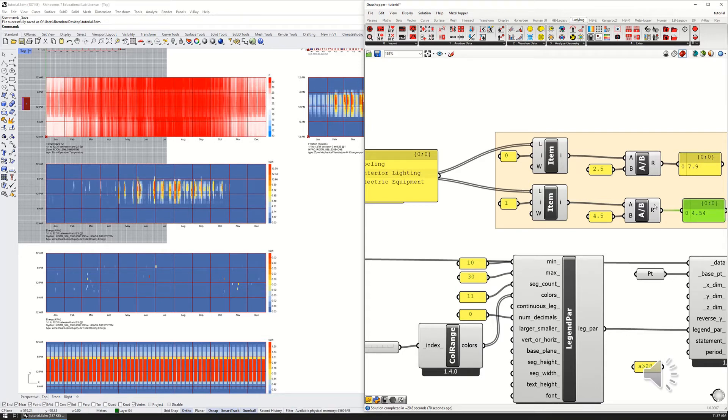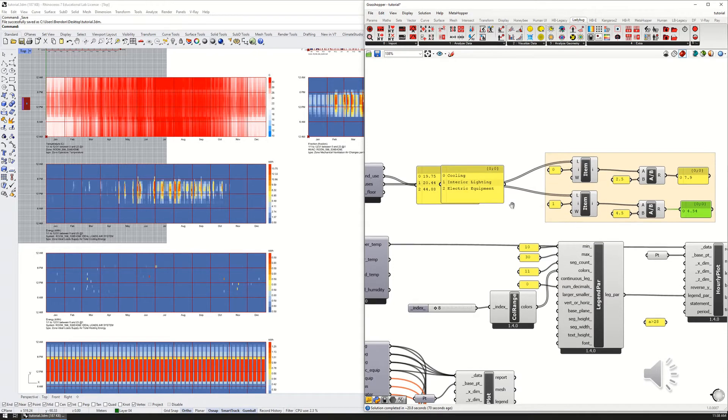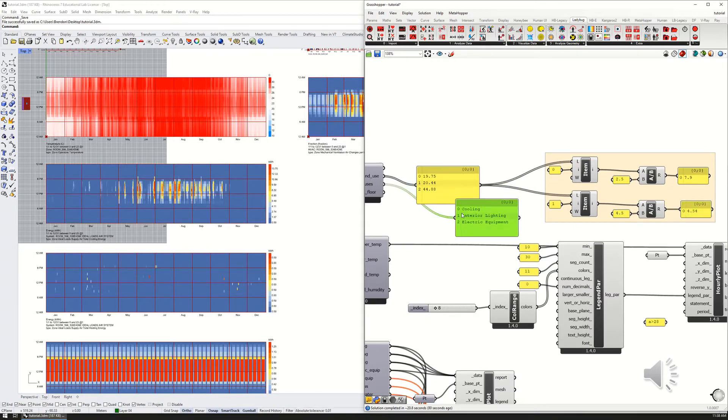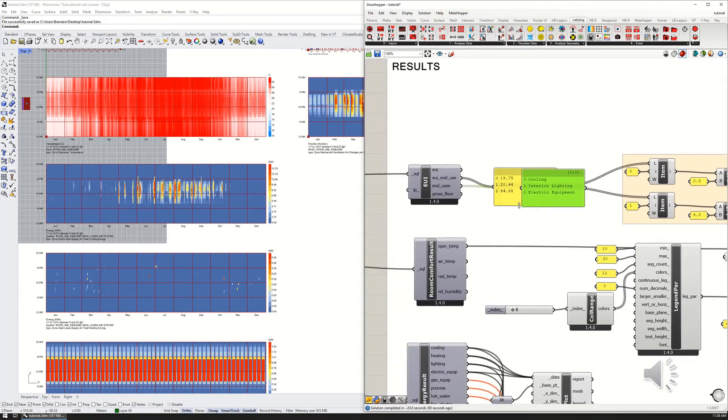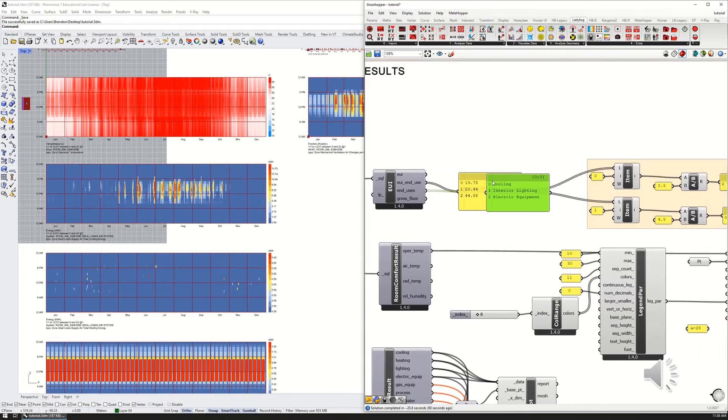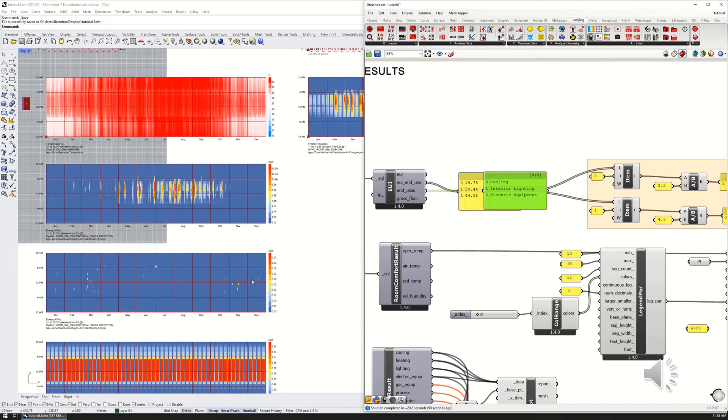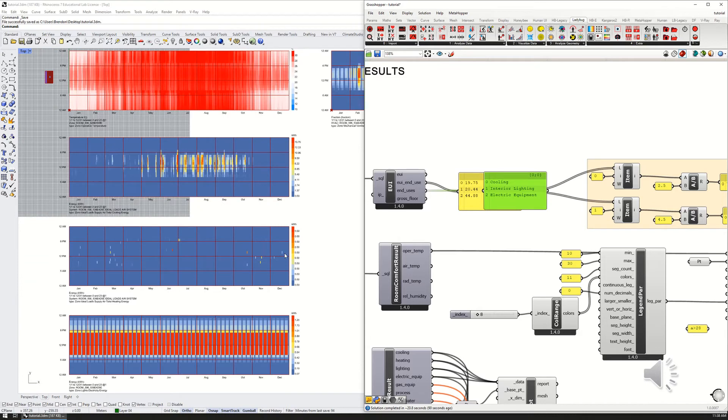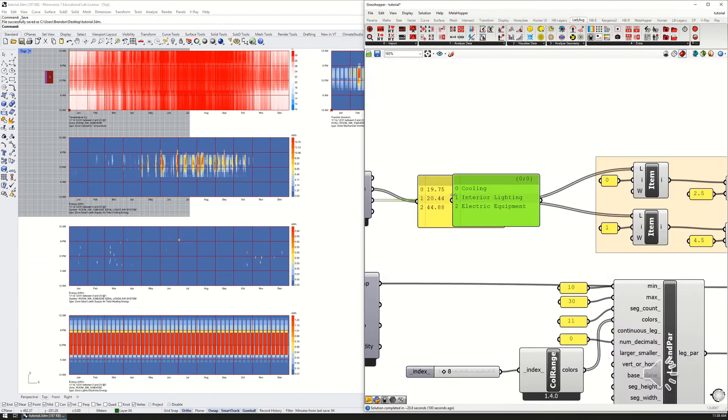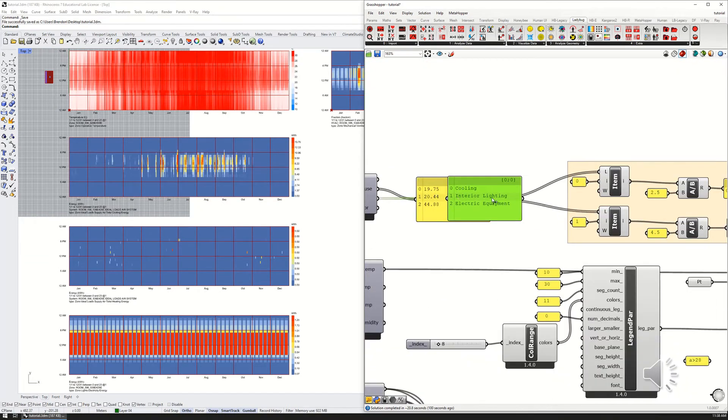And the heating has—oh, what's going on? Here's what's happened: there is no heating that's being reported here. Notice that it's dropped off this list completely. It's interesting, although it does show some times here, but it's basically zero for all of these, and our cooling has gone up to 19.75.